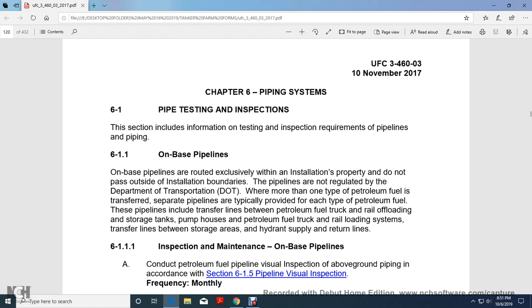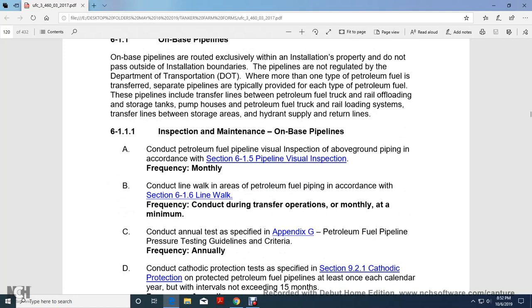The pipelines include transfer lines between petroleum fuel truck and railroad offloading, storage, pumps and pump houses, petroleum fuel truck and rail loading systems, transfer lines between storage areas, and hydrant supplies and return lines. Inspection, monthly, on-base pipeline lines. A. Conduct the petroleum fuel line pipeline visual inspection of above ground pipeline in accordance with 6-1.5 pipeline visual inspection. B. Conduct a line walk of the area of the petroleum fuel piping in accordance with 6-1.6 line walk. Frequency: conduct during transfer operation, monthly at the minimum.